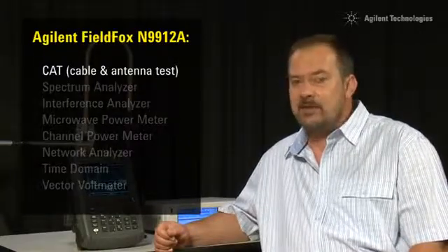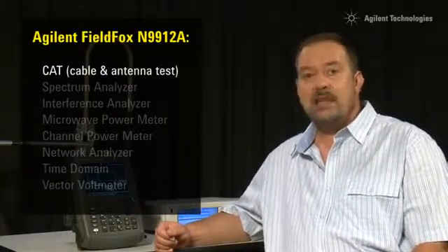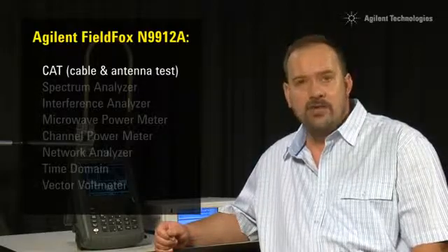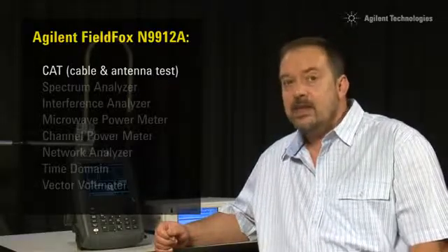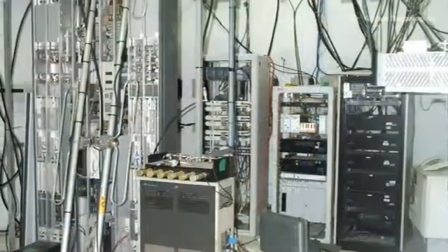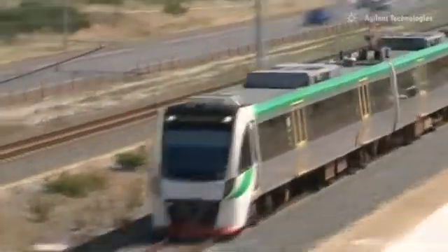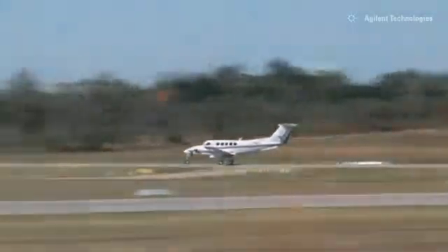In its most basic configuration, it's an extremely comprehensive cable and antenna tester, covering 2MHz to 6GHz. So, we can test everything from HF radio, broadcast transmitters, land mobile two-way radio, air band, marine band and all mobile phone bands, 2.4GHz and 5.8GHz Wi-Fi and all frequencies in between.